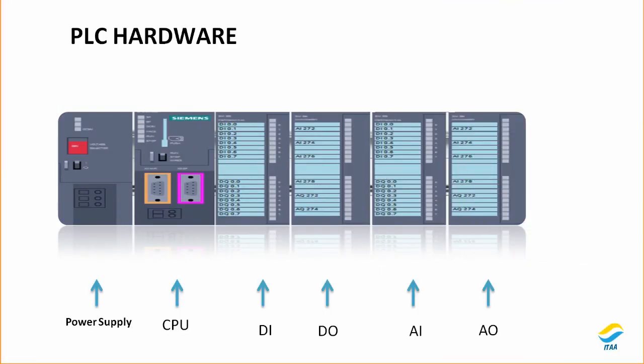So the PLC hardware is right in front of you. Power supply comes in the first slot of the rack, and the second slot you have a CPU. CPU is the brain of the PLC. Now if you want to process the digital signals, DI digital input card will come in here, and digital output card right after that. And then if you have some analog signals, by analog signals I mean like the signals that are continuously changing, for example temperature, level, pressure, flow, these are analog signals.